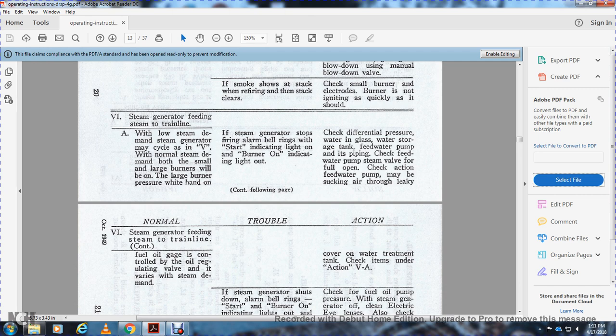Check the differential pressure, water gauge and glass, water storage tank, and the feed water pump with the piping. Check that the feed water pump steam valve is fully open. Check the action: the feed water pump may be sucking air through the leaky cover of the water treatment tank. Check the items under the action 5A.